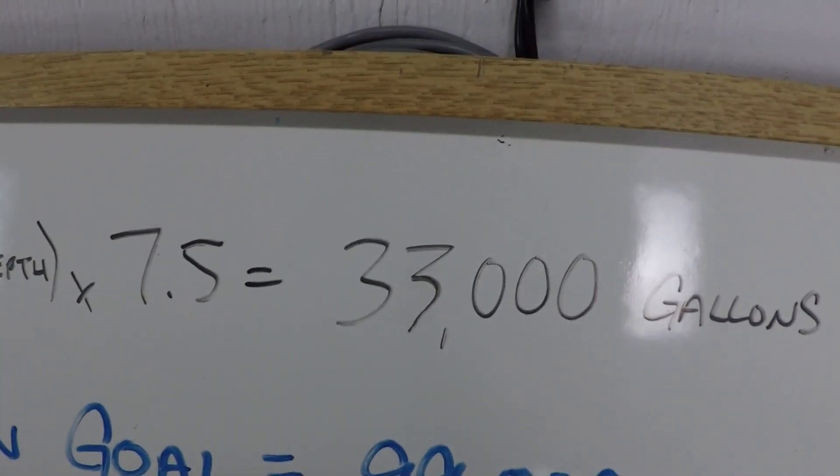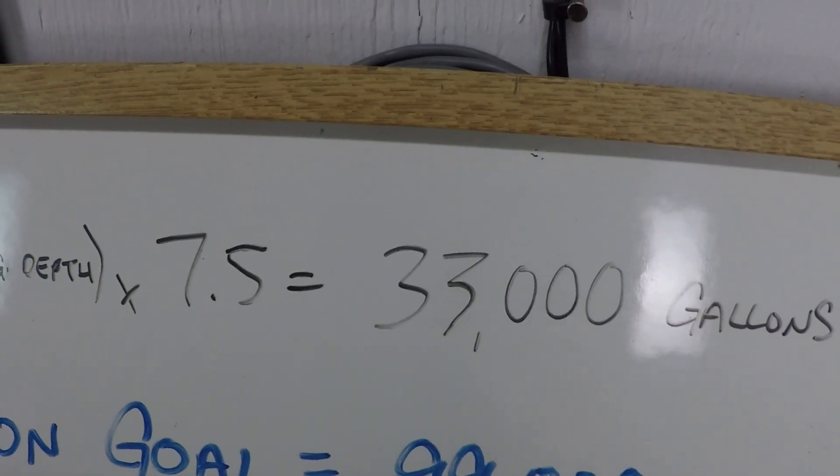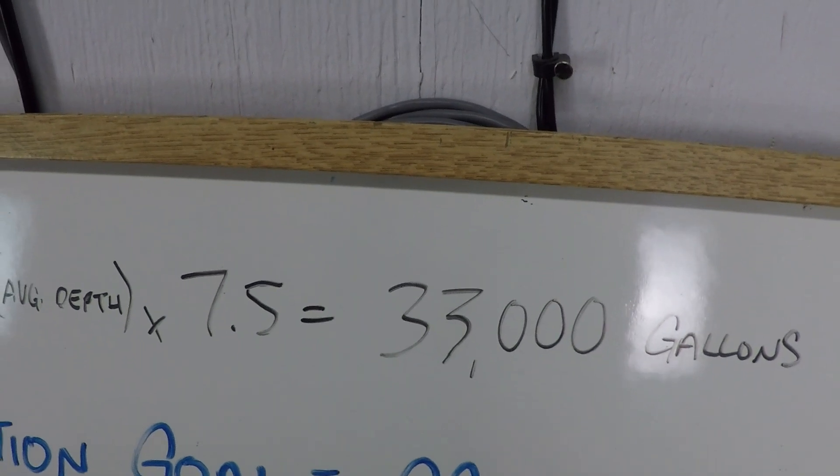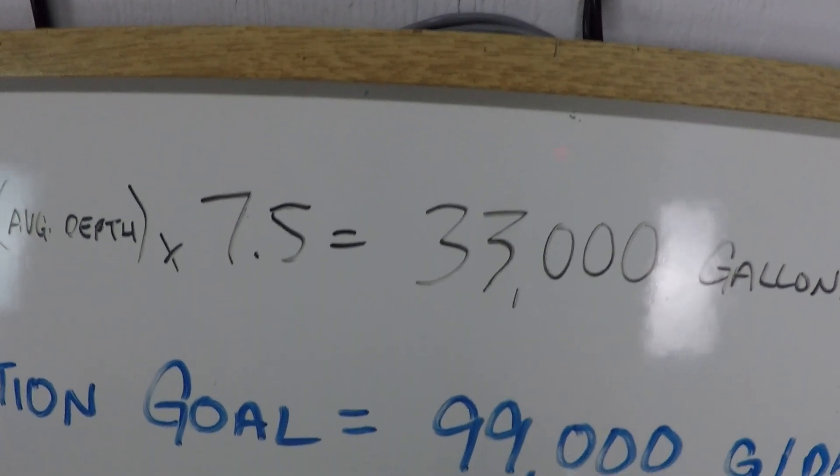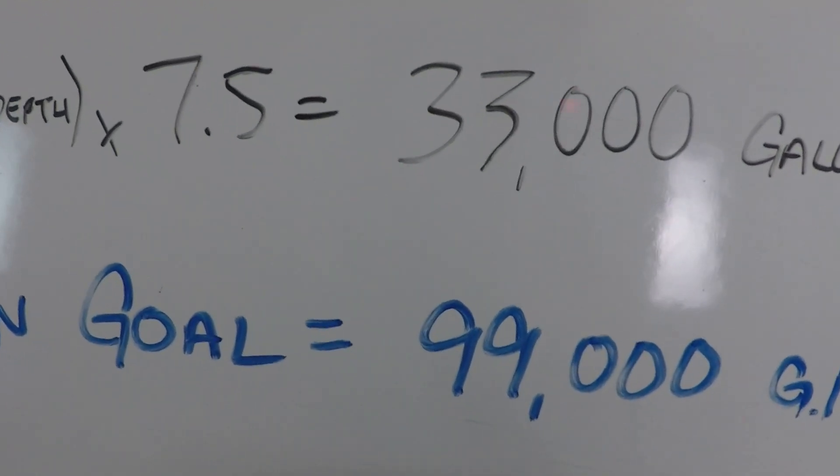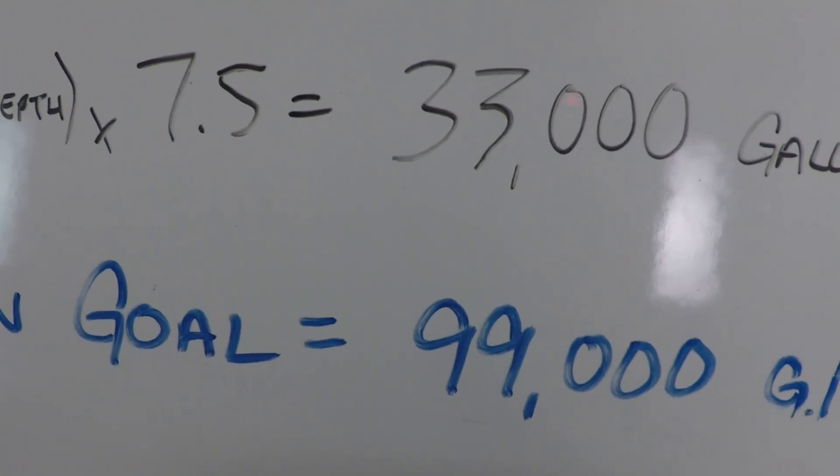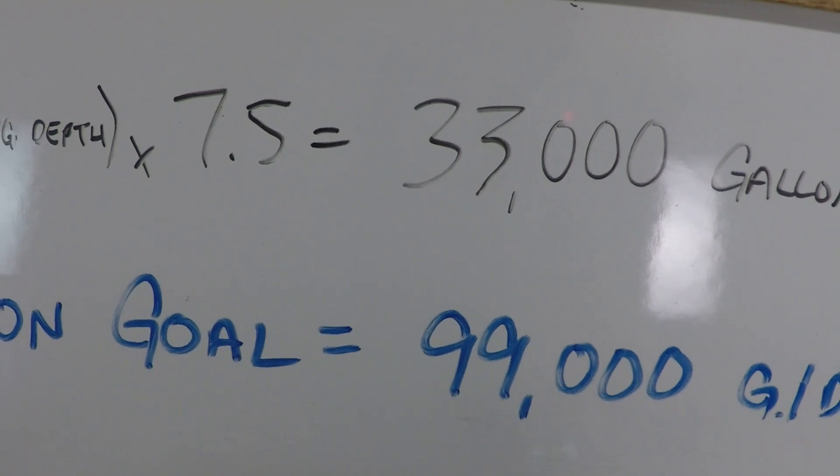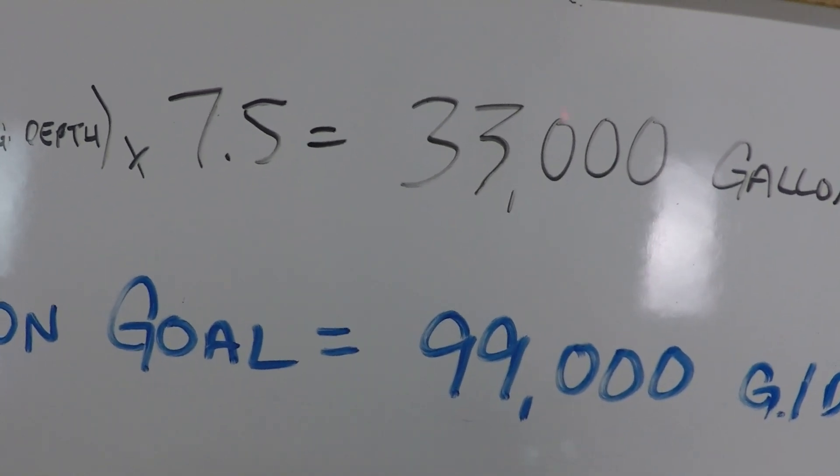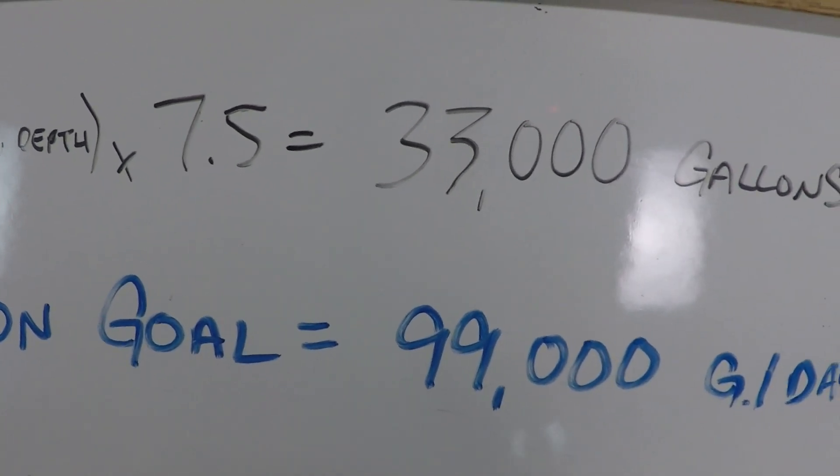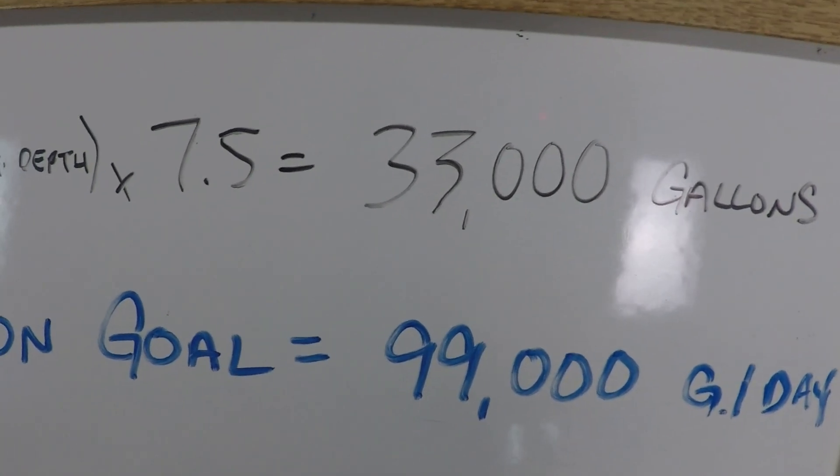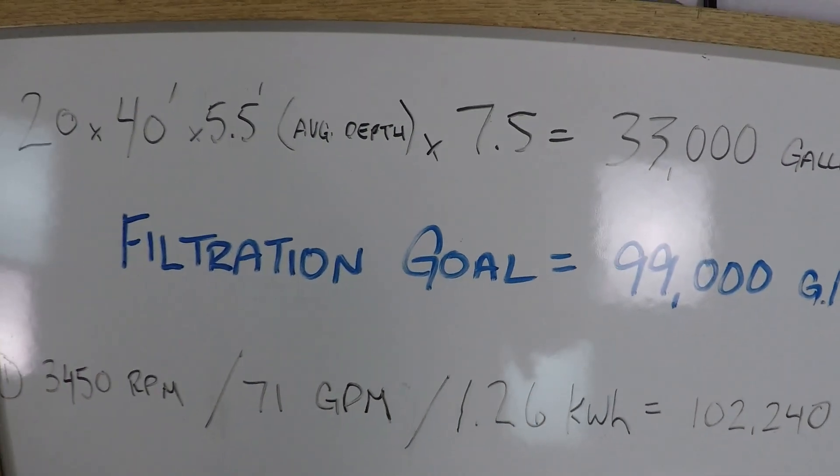If you only filter 33,000 gallons in a day, you don't actually get all of the water. Some of it gets done twice or three times and a lot of it doesn't get done at all. By the time you filter three times the volume of the pool, you're achieving approximately 95% of all of the water in your pool being filtered at least one time. So for this example, we're going to call this the minimum amount of filtration that we're aiming for, 99,000 gallons.